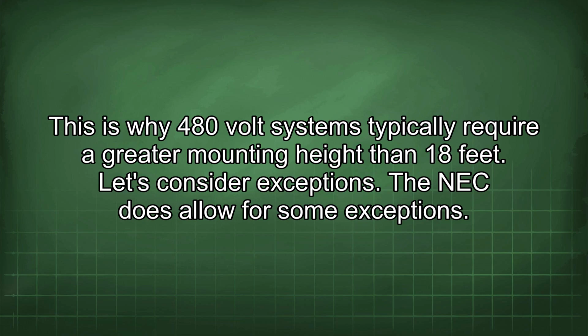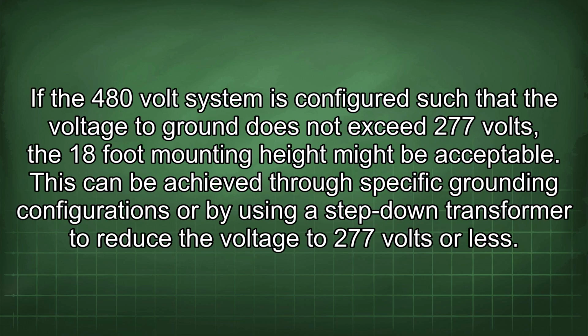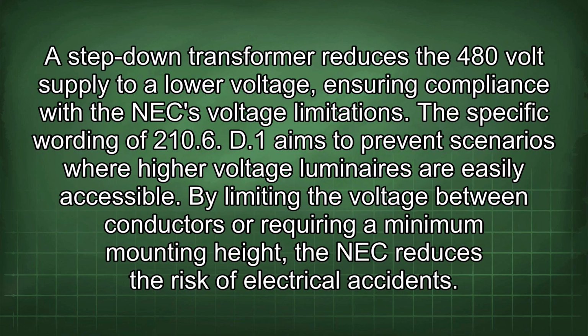Let's consider exceptions. The NEC does allow for some exceptions. If the 480-volt system is configured such that the voltage to ground does not exceed 277 volts, the 18-foot mounting height might be acceptable. This can be achieved through specific grounding configurations or by using a step-down transformer to reduce the voltage to 277 volts or less. A step-down transformer reduces the 480-volt supply to a low voltage, ensuring compliance with the NEC voltage limitations. The specific wording of 210.6(D)(1) aims to prevent scenarios where higher voltage luminaires are easily accessible. By limiting the voltage between conductors or requiring a minimum mounting height, the NEC reduces the risk of electrical accidents.